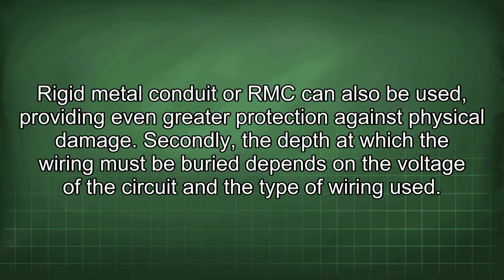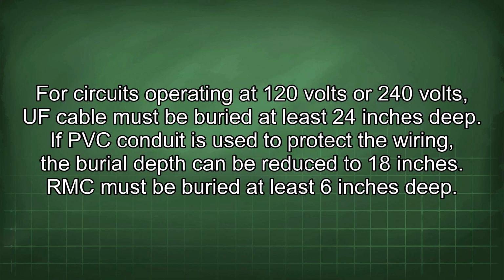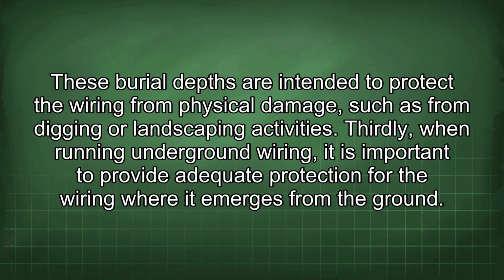Secondly, the depth at which the wiring must be buried depends on the voltage of the circuit and the type of wiring used. For circuits operating at 120 volts or 240 volts, UF cable must be buried at least 24 inches deep. If PVC conduit is used to protect the wiring, the burial depth can be reduced to 18 inches. RMC must be buried at least 6 inches deep. These burial depths are intended to protect the wiring from physical damage, such as from digging or landscaping activities.